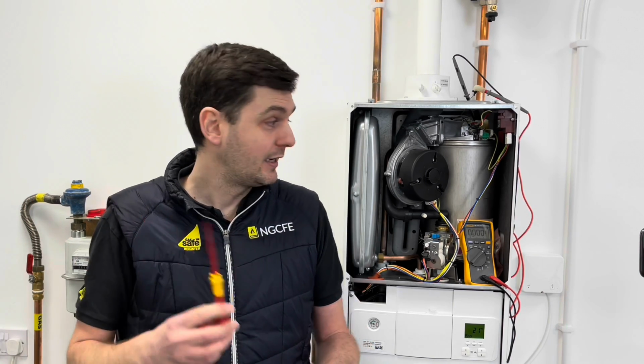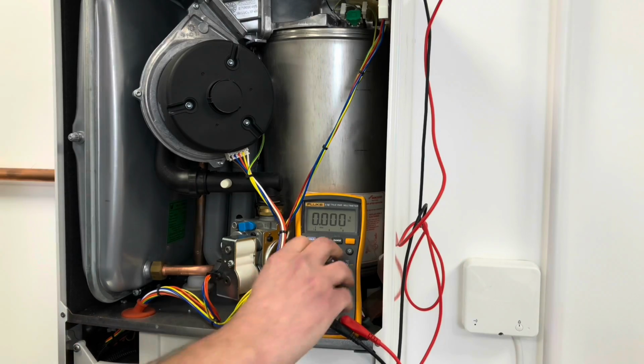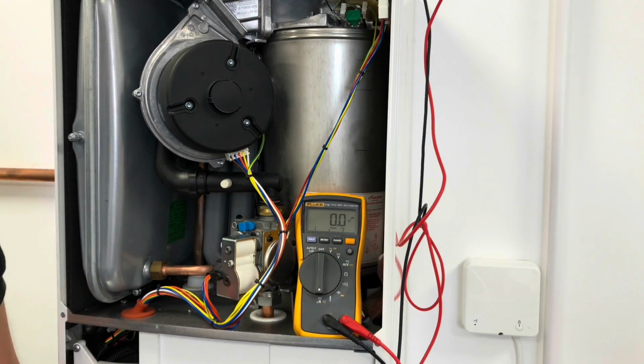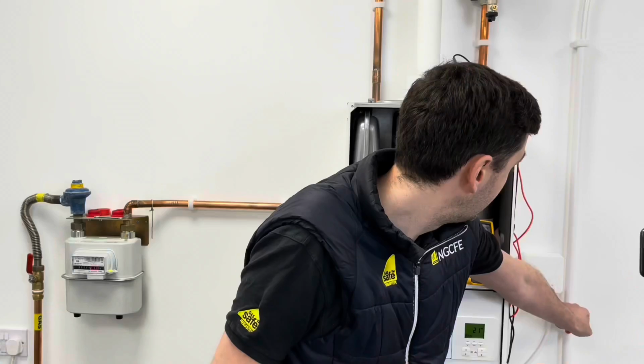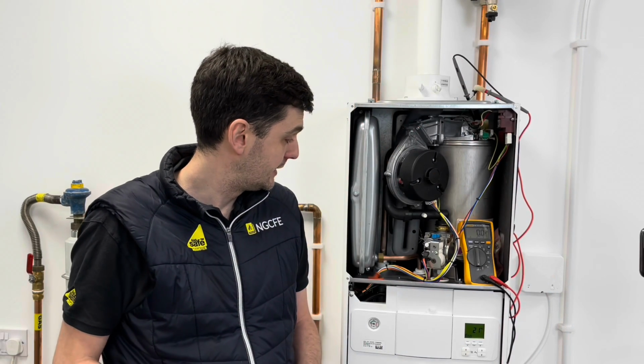Other things we need to look out for with rectification probes, that there's no breaks in them. And also it could be that you've got an issue with the board, so the board might be receiving it but it's just not registering that the voltage is coming back as DC. The microamp setting, again, I find it really useful, but not all multimeters have it. So let's see what amperage we get if we turn the boiler on.